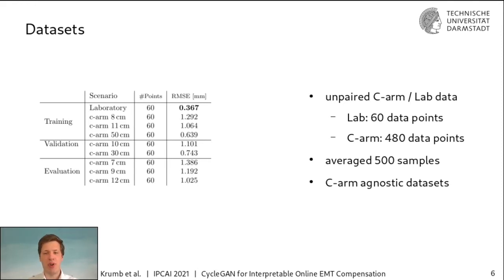All of the measurement points are results of 500 samples being averaged in static measurements. Something that also has to be noted is that all of these measurements are C-arm agnostic, so we do not store the C-arm orientation and position with respect to the electromagnetic tracker. This is not a feature that we use in our approach.